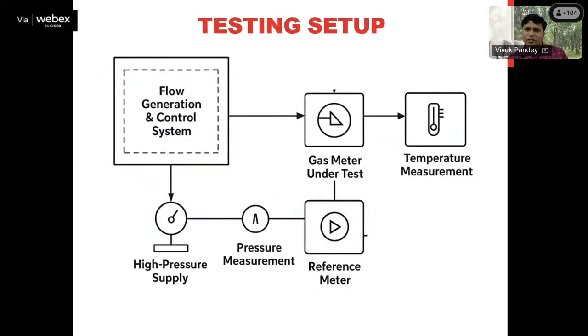Now when we talk about a general flow diagram for the testing setup, this can be a picture, not exact, but more or less, this can be a good setup for the accuracy test. Suppose a gas meter under test is connected in cascade with the reference gas meter, or you can say master meter. In cascade means the gas will pass through the reference meter as well as the gas meter through the same pipeline. And for the measurement of pressure, we need manometers, and we should measure the pressure of gas supplied through the pipeline in the testing setup continuously.